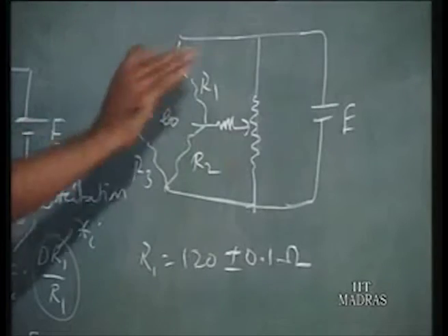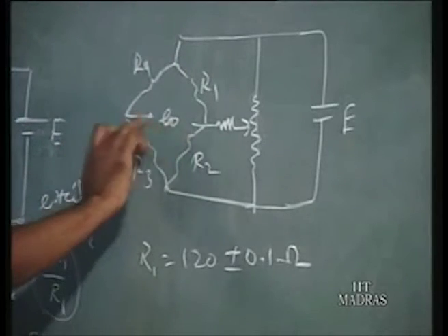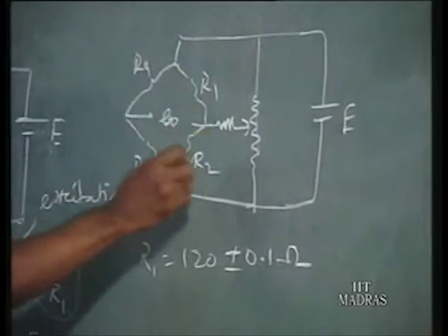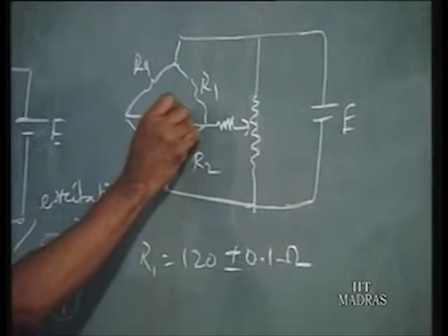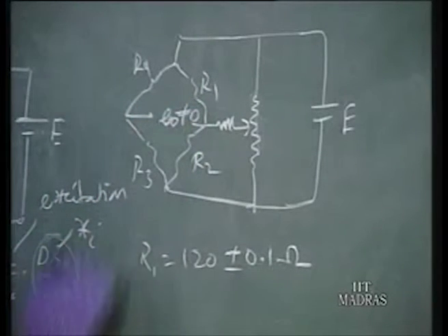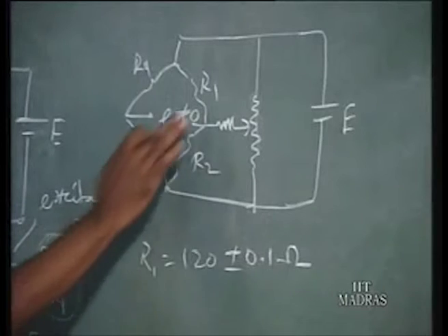So even though we don't change any one of them by giving an input signal, say in a cantilever load cell, we don't give any force, still the moment you connect them into a bridge and give excitation voltage, you will have EO not equal to 0. That means they are not equal. How to make them equal? That is what is done.